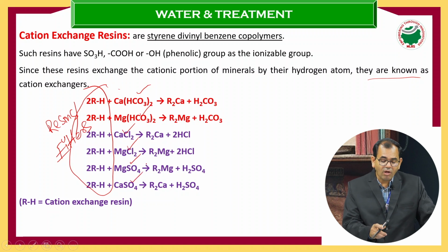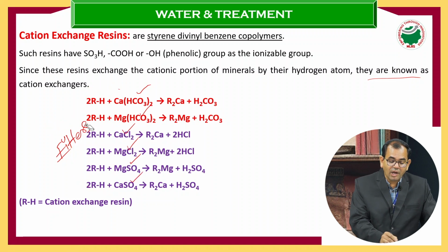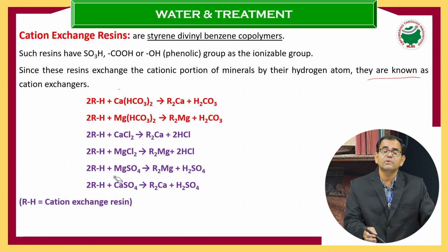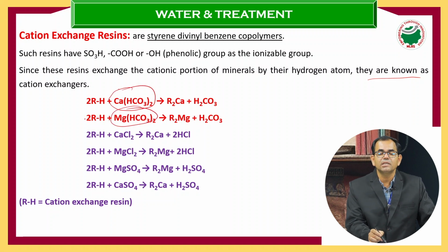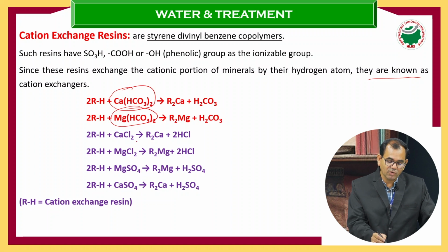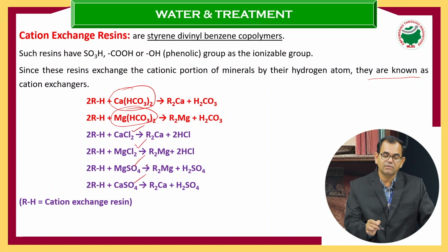All these are hardness causing salts. Calcium bicarbonate and magnesium bicarbonate are temporary hardness causing salts. Calcium chloride, magnesium sulfate, calcium sulfate are permanent hardness causing salts, which are there in the feed water.